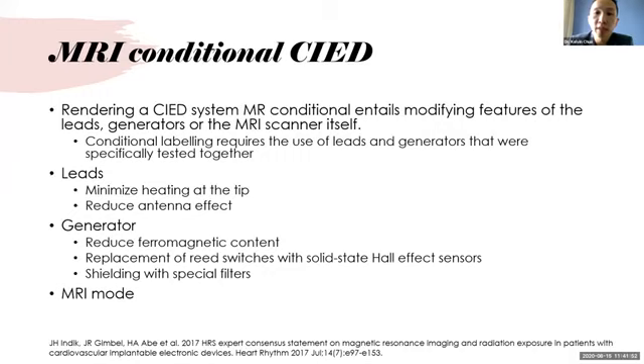So for the leads, the two main challenges are to minimize the heating at the tip and to reduce the antenna effect. The heating at the tip can cause myocardial damage, pain, and changes in pacing and sensing function, while the antenna effect picks up resonant frequency and causes electric current to conduct and possibly myocardial capture, and that can induce arrhythmias. The generator, on the other hand, faces maybe more challenges. Manufacturers have to reduce the ferromagnetic content to decrease magnetic attraction and imaging artifacts. Reed switches are replaced with solid-state Hall effect sensors, which behave more predictably in an MRI environment.